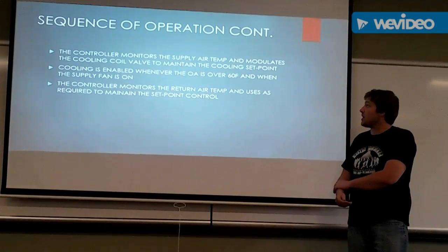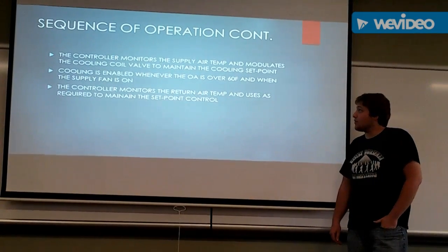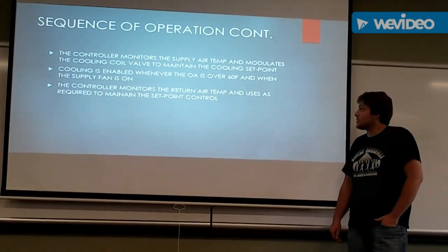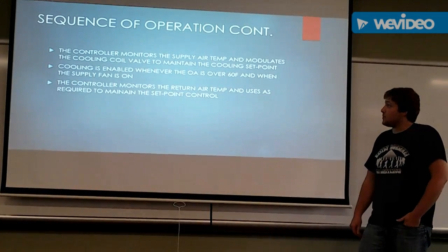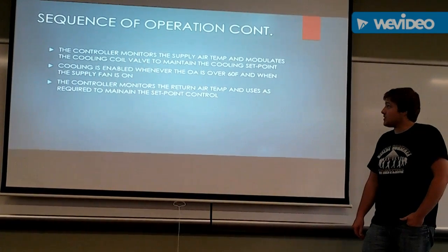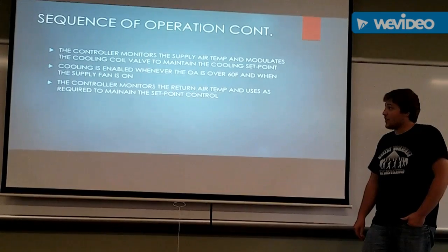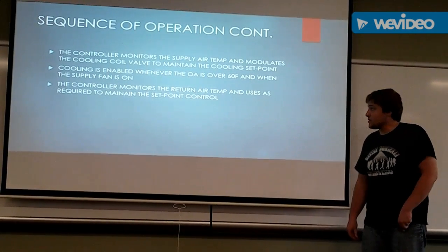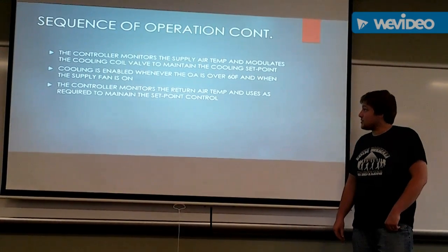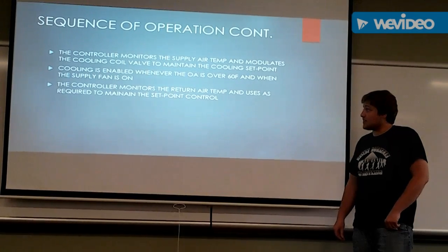Monitors the supply air temp and modulates the cooling coil valve to maintain the cooling set point. Cooling is enabled whenever the outdoor air is over 60 degrees Fahrenheit and when the supply fan is on. The controller monitors the return air temp and uses it as required to maintain the set point control.